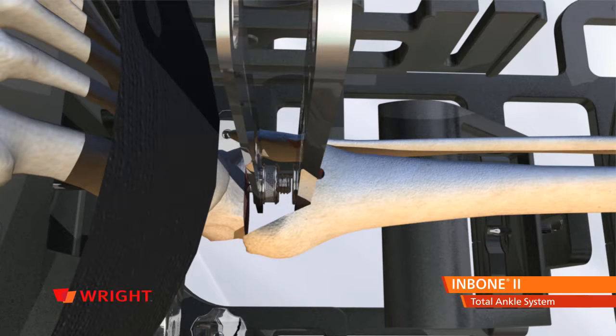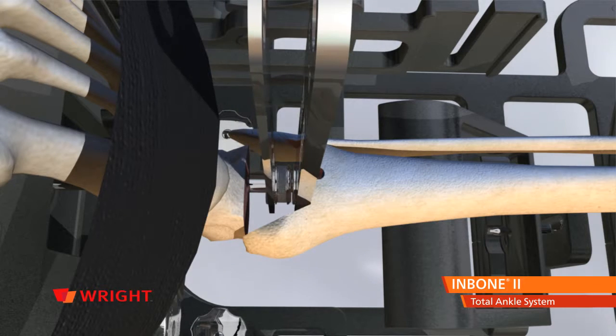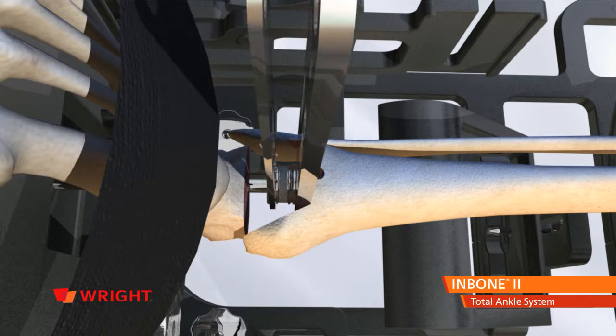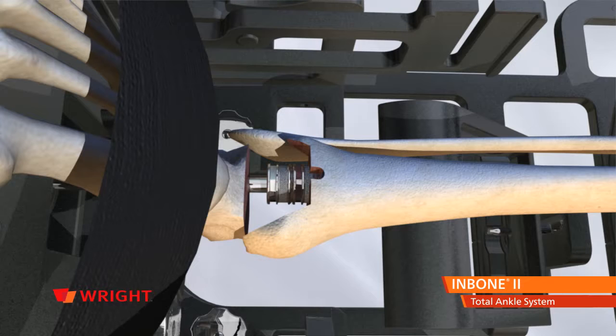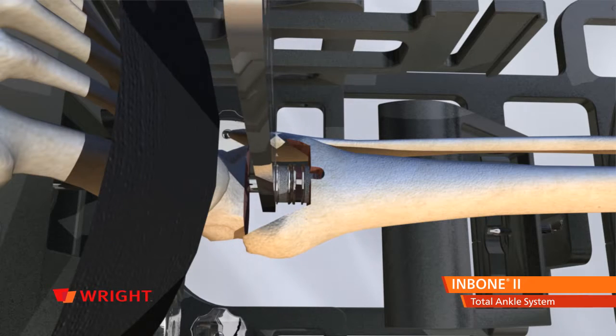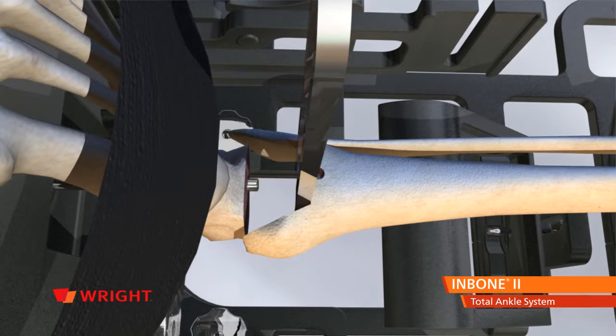Insert a mid-stem piece onto the clip and align the mid-stem with the top stem piece. While an assistant holds the wrench, engage the X drive. Thread the stems and firmly torque them together. Remove the clip from the mid-stem piece and replace it with the wrench from the top stem piece before pushing the stem up into the tibia. Repeat for additional mid-stem components.